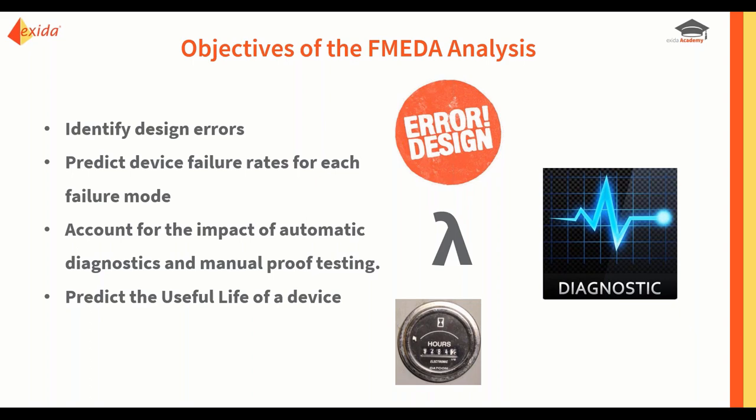Again, I previously came from the medical device sector, and an example I remember from working there was where a fairly big medical device manufacturer decided to redesign an ECG machine using a new component that had been released to the market. The importance of the useful life there is they had no data to understand how long that component would last in an operational environment. As it turned out, the component was failing 3 to 4 years after use, but the expected lifetime of an ECG machine would be 8 to 10 years. So serious consequences there for not checking into the useful life of the component.